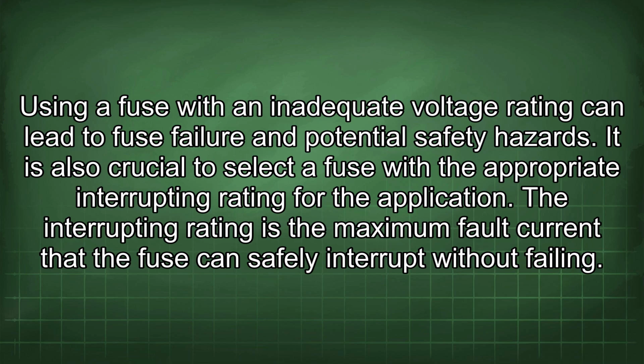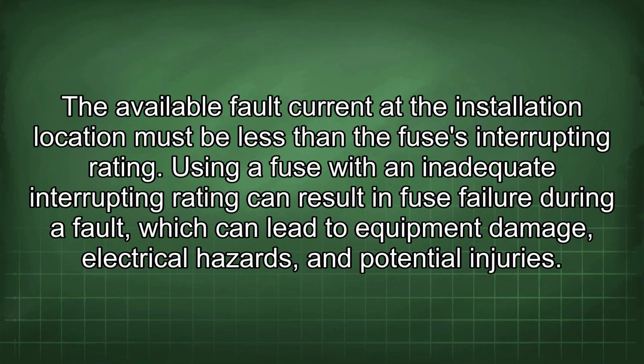Using a fuse with an inadequate voltage rating can lead to fuse failure and potential safety hazards. It is also crucial to select a fuse with the appropriate interrupting rating for the application. The interrupting rating is the maximum fault current that the fuse can safely interrupt without failing. The available fault current at the installation location must be less than the fuse's interrupting rating. Using a fuse with an inadequate interrupting rating can result in fuse failure during a fault, which can lead to equipment damage, electrical hazards, and potential injuries.